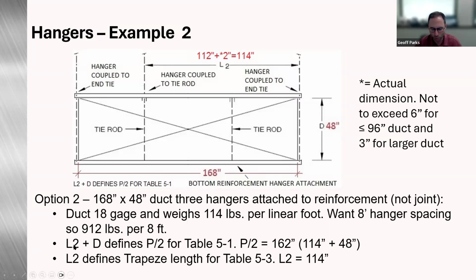We would take the L2 plus our DD, which is 2 inches for this one. And that again, that's going to define our P half perimeter, P divided by 2, for table 5-1. So P divided by 2 is equal to 162 inches. So our 114 plus our 48. And then L2 also defines our length, to select our trapeze from table 5-3. And that length is going to be 114. So based off of our L2 plus the 2 inches.